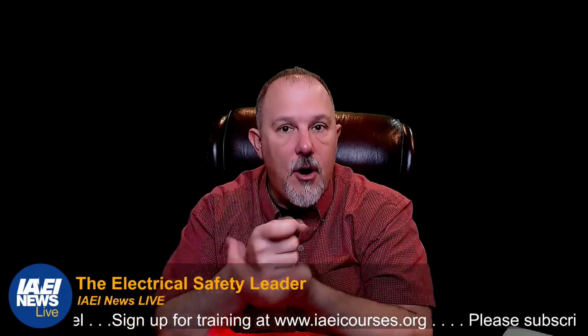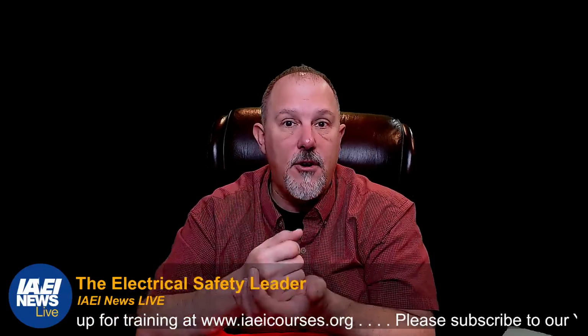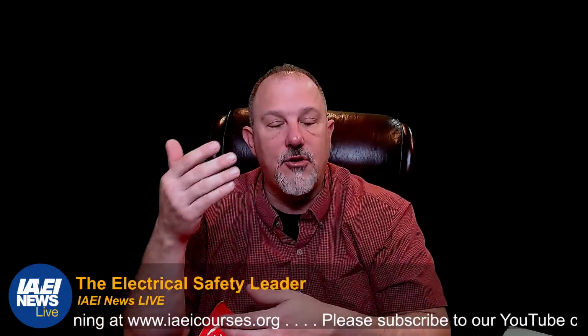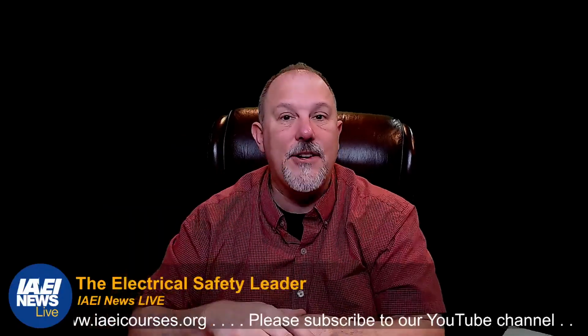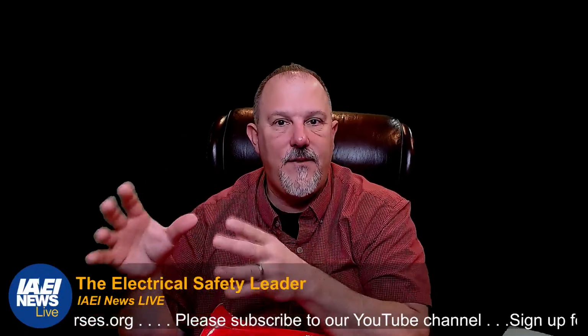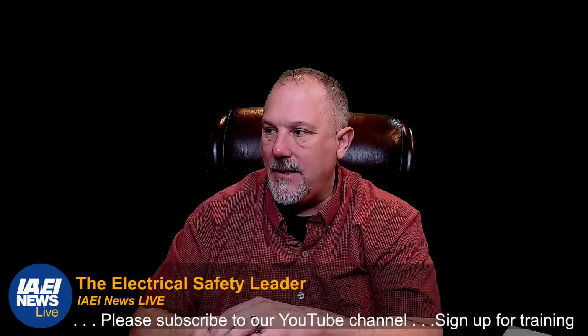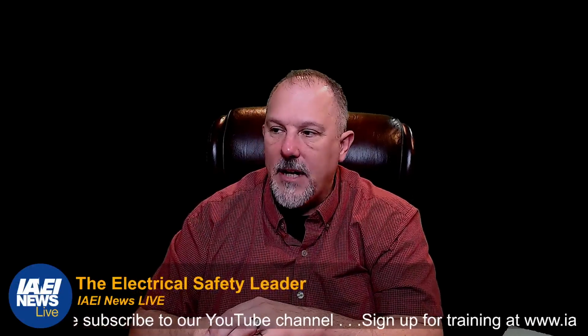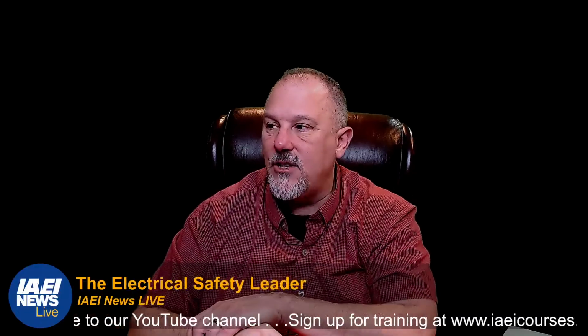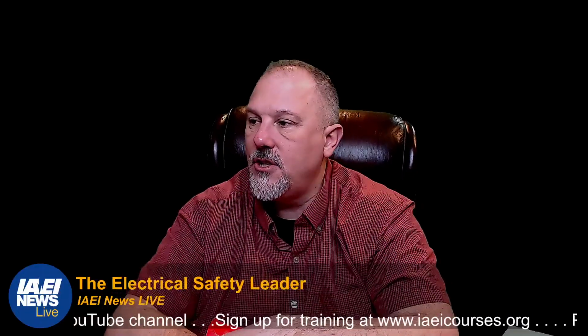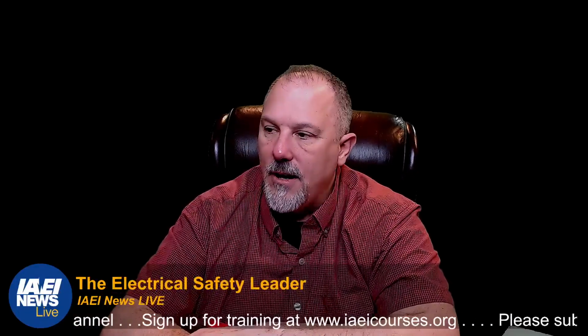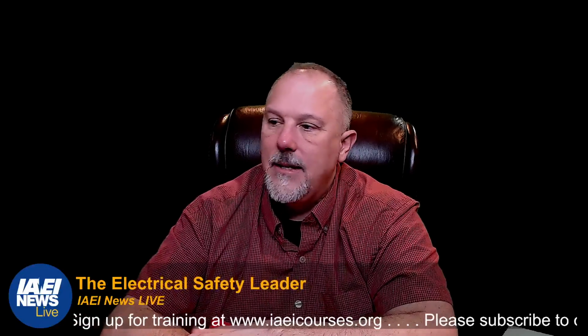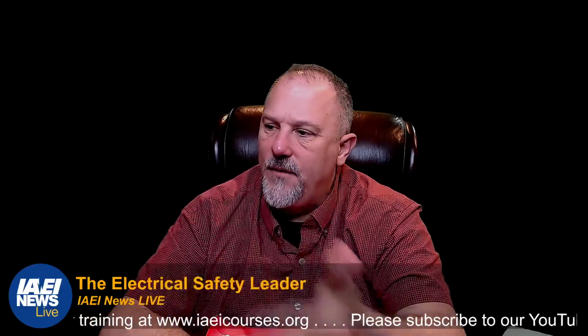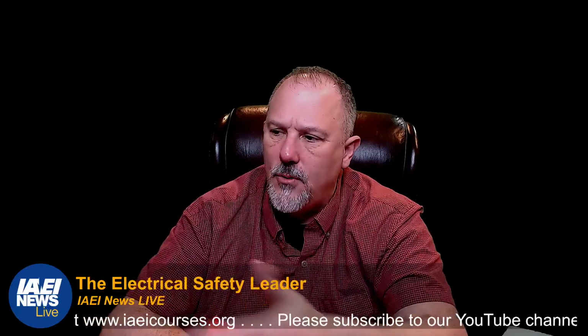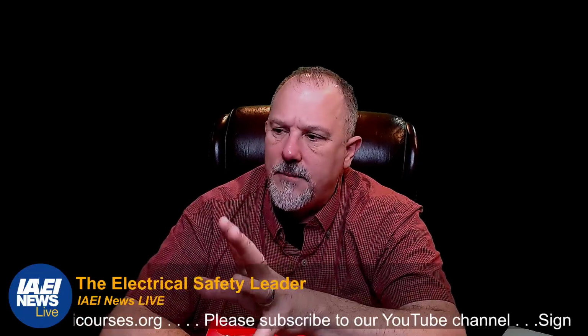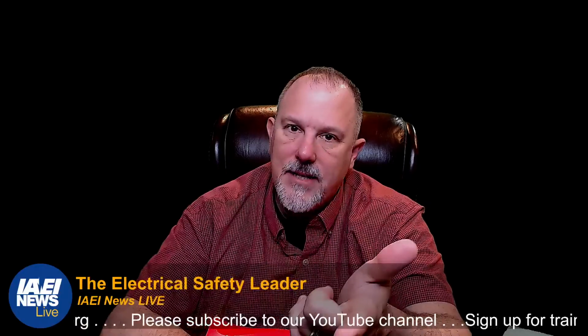You might do thermography. Chapter 7 tells you how to do thermography. You might inject current and measure temperatures. Chapter 7 will tell you how to do that. Any of those tests in the field, Chapter 7 is going to give you that guidance. Verify lubrication on moving current carrying parts and sliding surfaces. See the manufacturer's instructions. You're going to verify interlock systems for correct sequencing. Verify filters are clean and in place, fuse holders, etc. So there's 11 items. The 11th item, again, is that catch-all.